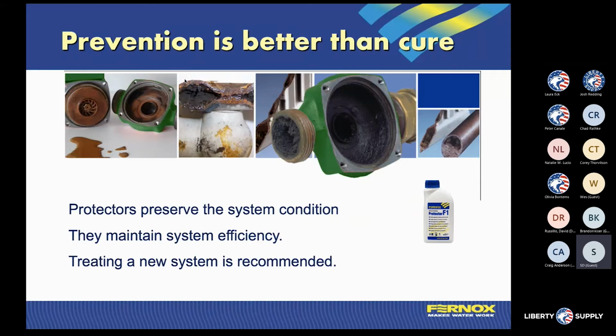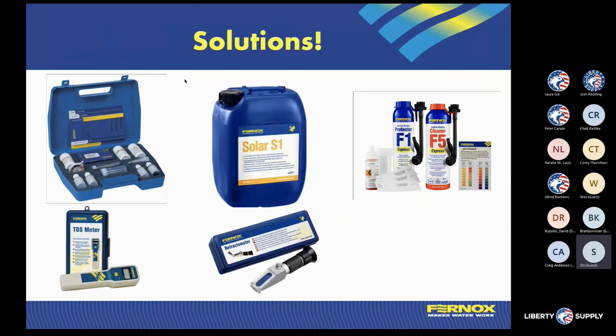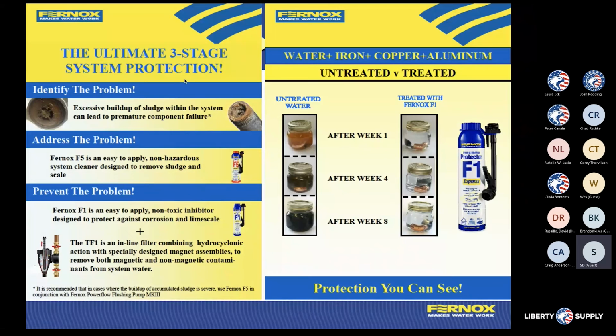We're going to talk about that from a couple of different spaces here. We're going to talk about how we create the solution, and we're going to utilize Fernox products to create a solution that we're going to be able to put into the system, and that's going to help us balance our inhibitor levels and get to a place where that system stops corroding or getting worse from where it's at this point. So we're going to have a three-step initial process. If there's something that's broken or a system where something has failed, you've identified you have a problem, and then we're going to talk about how we get to a solution for that system.